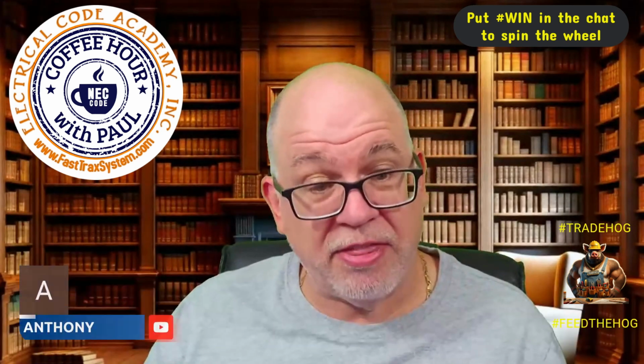What did he say? What do you do about the XO in the delta? Well, if you have a delta and you have an XO, then you do nothing with it, okay? If you're not deriving a neutral, and if you even have an XO in a pure delta scenario, do nothing with it. Is it a violation to bond it? Well, it depends to what. If there is an XO, that means there's a neutral point. Otherwise, you wouldn't need the XO.